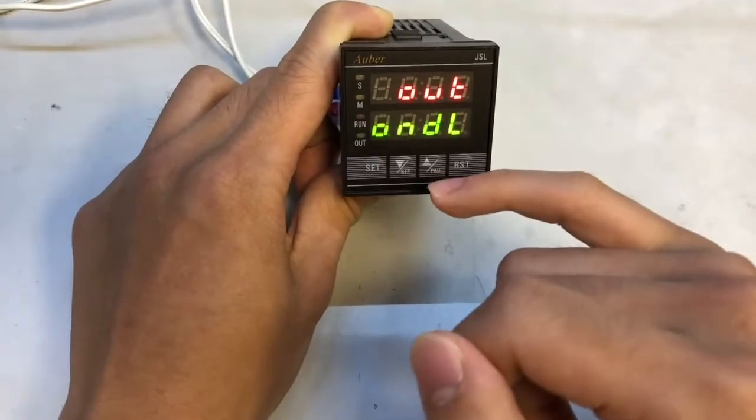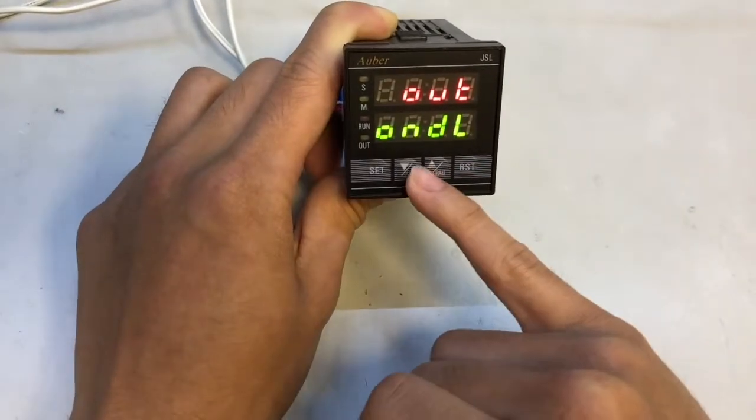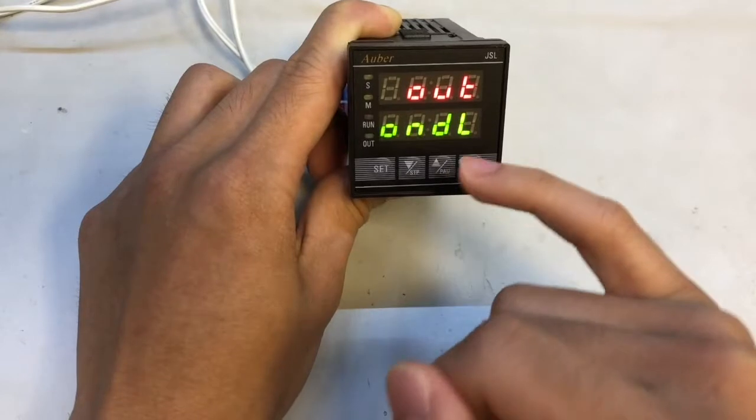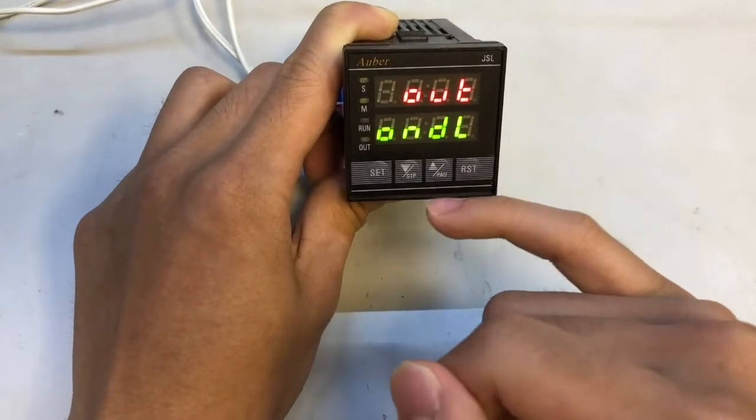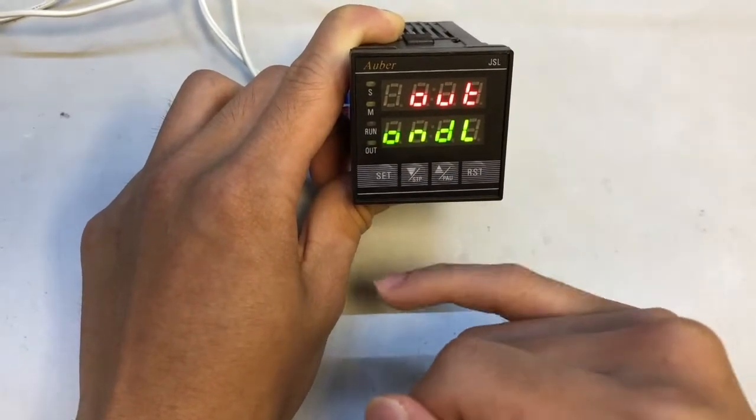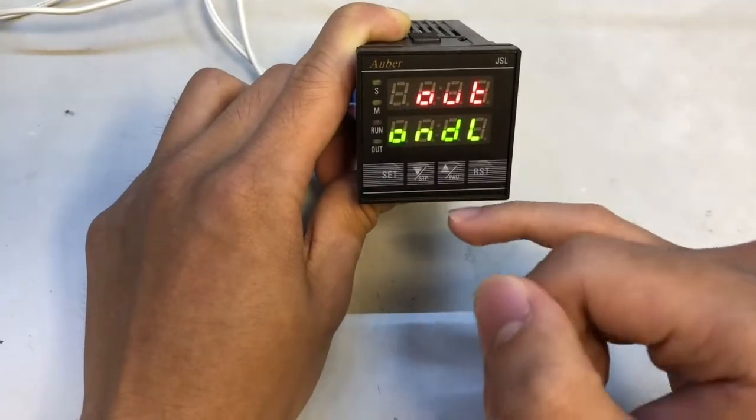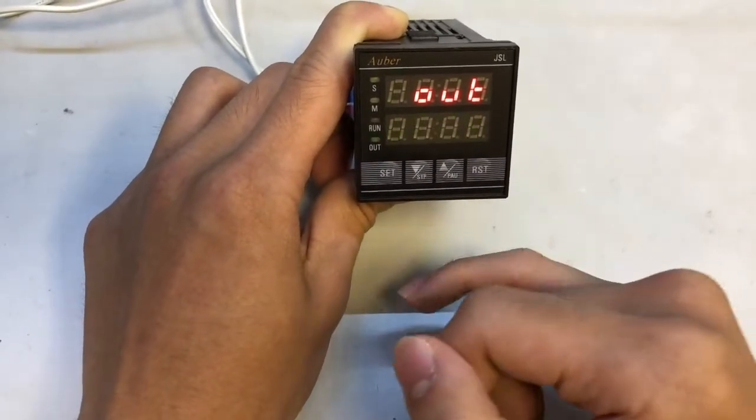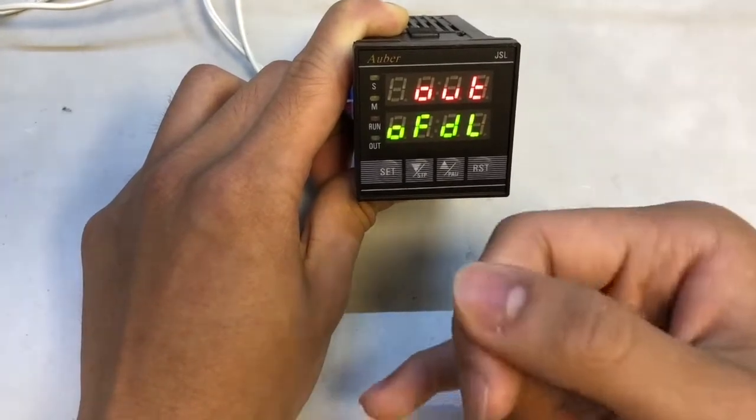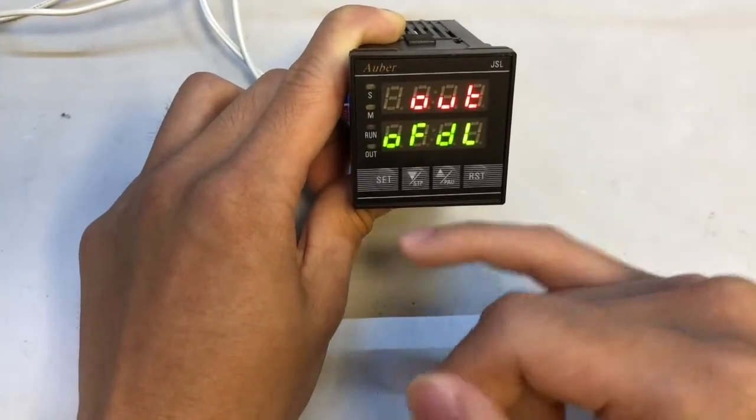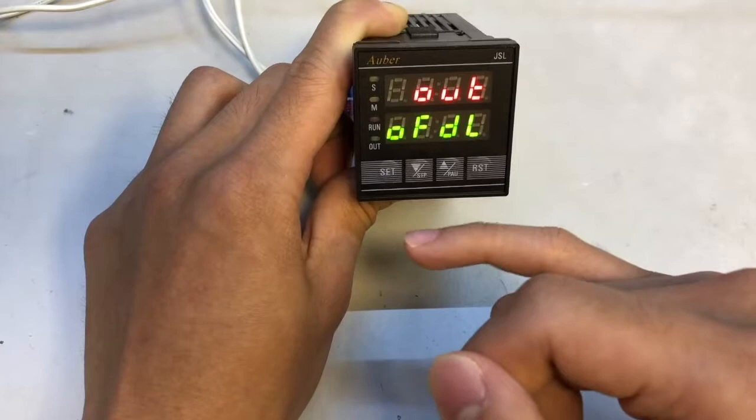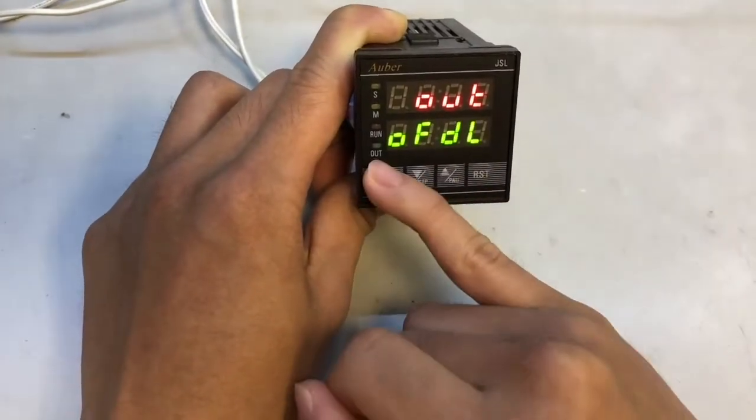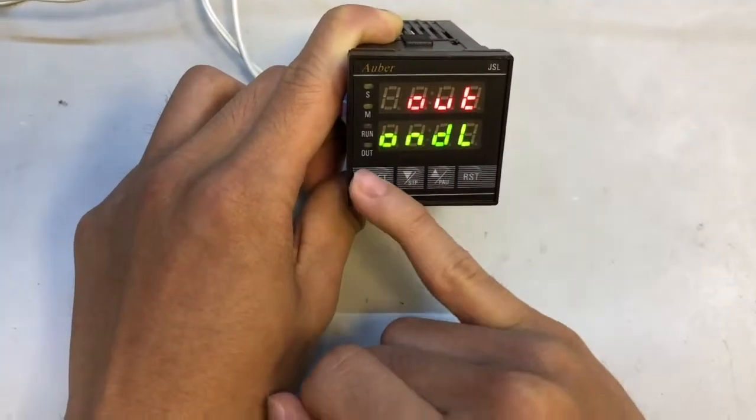This is our output mode. There's two different settings: ONDL or on delay, where the relay will stay off at the start of the timer and switch on once the timer reaches the set time. And you have your OFDL or off delay, which is the complete opposite - the relay will be on and then switch off once the timer reaches the set time. We're just going to keep it ONDL or on delay.